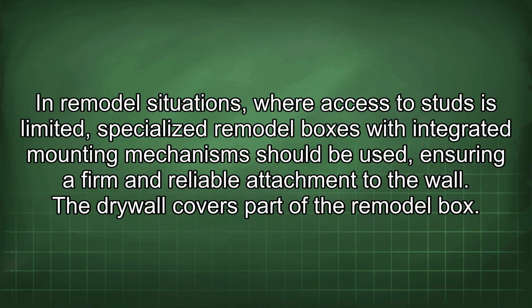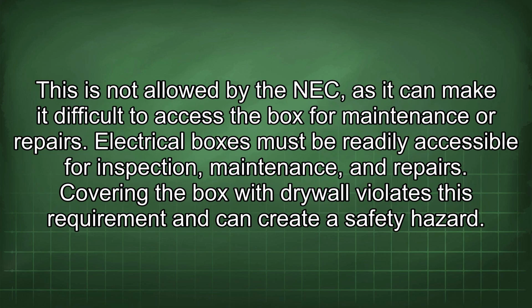In remodel situations where access to studs is limited, specialized remodel boxes with integrated mounting mechanism should be used, ensuring a firm and reliable attachment to the wall. Drywall covers part of the remodel box. This is not allowed by the NEC as it can make it difficult to access the box for maintenance or repairs. Electrical boxes must be readily accessible for inspection, maintenance, and repairs. Covering the box with drywall violates this requirement and can create a safety hazard.